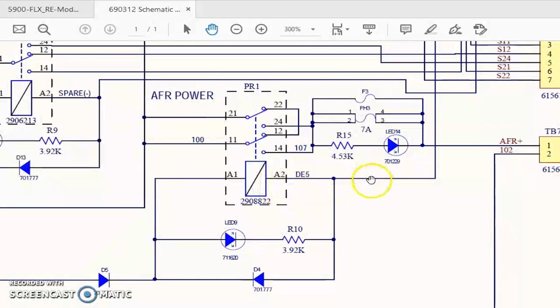But if I don't have this circuit grounded and I measure this DE5 connection back at the digital output 5 and I hadn't switched on the ground, I'm likely to see 24 volts with a digital volt ohm meter. And that is because with a not completed circuit, the resistance factor that's taking place in here and right here is irrelevant until I complete the path of the circuit. So as soon as I ground this circuit, the voltage will dissipate and drop to 0, or should, provided my ground path is sufficient enough to handle the voltage that remains after the resistance. That's a short, quick example of voltage potential.